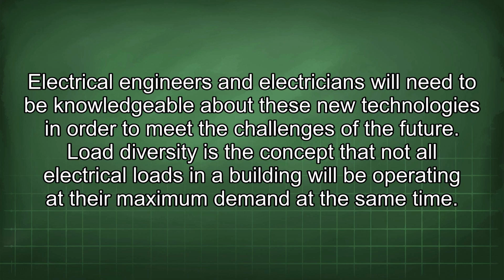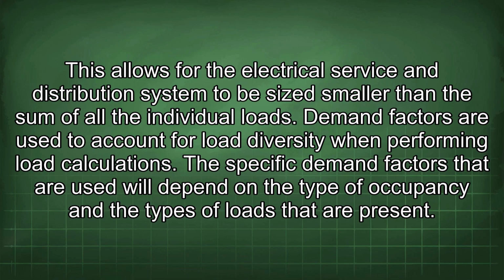Load diversity is the concept that not all electrical loads in a building will be operating at their maximum demand at the same time. This allows for the electrical service and distribution system to be sized smaller than the sum of all the individual loads. Demand factors are used to account for load diversity when performing load calculations.